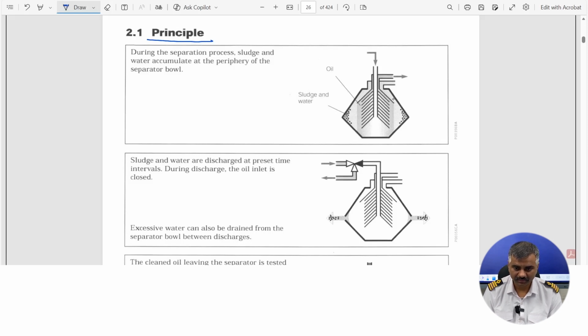We can see that the oil feed is coming in from this side, and this is the clean oil outlet. The water outlet is blocked by a valve, which is the V4 valve. Sludge and water accumulate like this at the surface. There is an interface here also, so don't think that there is no interface in the Alfa Laval purifier. There is an interface for the water and oil line. As the manual says, sludge and water accumulate at the periphery of the bowl, and the water rises inside through this outlet and goes out into this section.